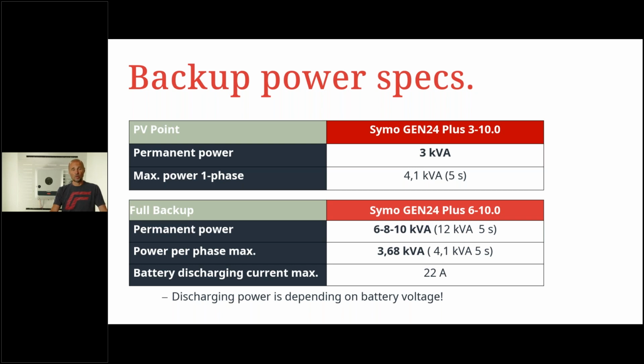That's also important sometimes for night consumption, because at night you need all the energy from the battery. Therefore we get 22 amps from the battery. If it's a 400-volt battery, so the bigger battery of BYD, for example, you will achieve about 9 kilowatt or kVA power from the battery. So that's also a kind of limitation. If you are using a small battery with only 200 volts, we are limited to 4.5 kVA. So therefore, in locations where you need more power, make sure that you also have the high battery voltage.